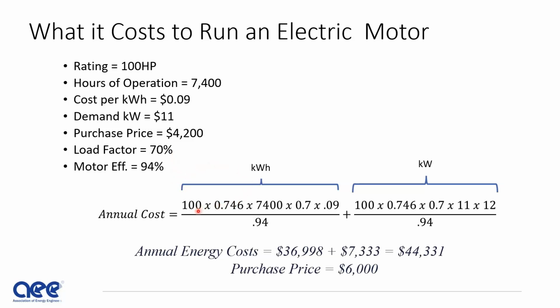So the kilowatt hours is going to be the 100 horsepower times 0.746, which is your conversion from horsepower to kilowatt, times the operating hours, times the load factor, times the cost per kilowatt hour, and divided by efficiency. What we have to add to that, though, is the demand cost, which is going to be the same conversion to kilowatt times 0.7 for 70% load factor, times $11 for demand, times 12 months for the year. And when we add these two together, you see that we're over $44,000 to operate a motor that costs $6,000.